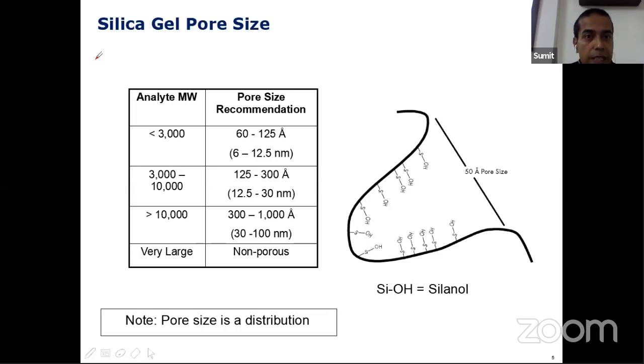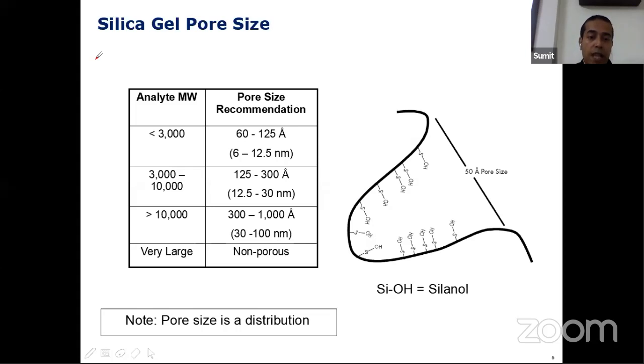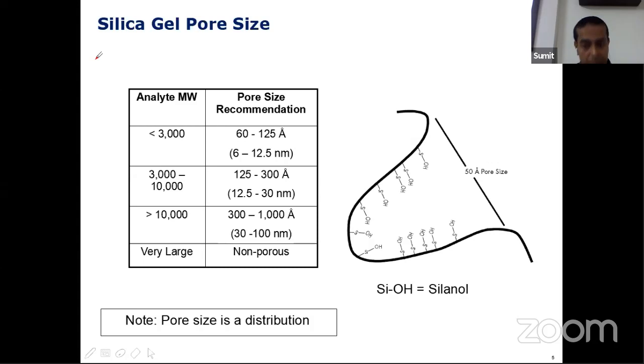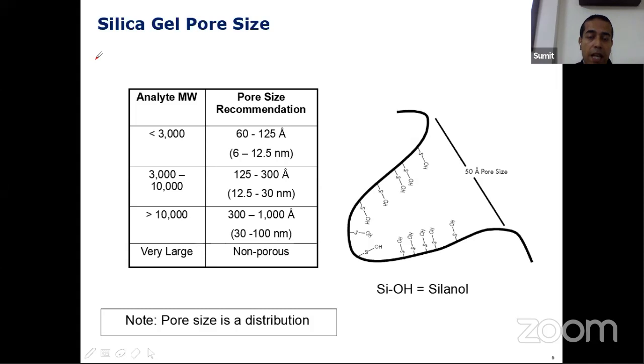The next parameter is the pore size. I have shown a table where analyte molecular weight is presented and pore size is recommended. We need to keep one thing in mind: pore size is never like a fixed size — you cannot make all pores identical, so they'll be in a range. Normally for drug compounds where the analyte molecular weight is typically less than 3000, a pore size of 60 to 125 angstroms is what we recommend. In a pore, you get to see a compound called silanol — silica bonded with a hydroxyl group.